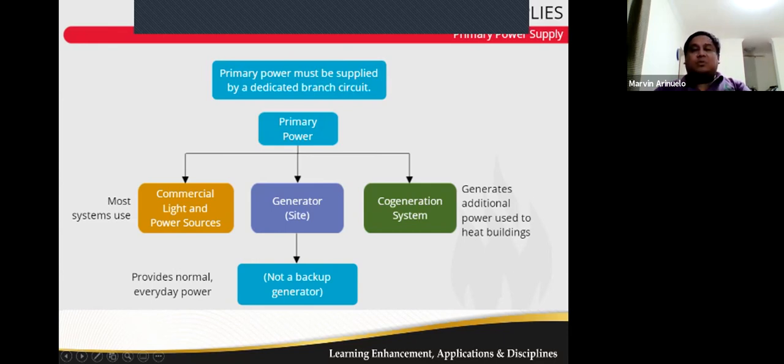It might supply several power supplies within a control unit or within multiple interconnected units serving the signaling system. And there is no requirement in NFPA for the power to be tapped ahead of a disconnect, and the dedicated branch circuit may come from a sub panel.